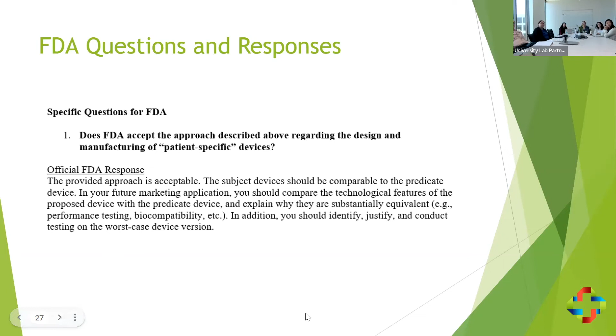All right, so this is one of the questions we got from FDA. I've kind of redacted some stuff in here. Does FDA accept the approach described above regarding the design and manufacturing of patient-specific devices? And they say, the nice thing, the provided approach is acceptable. The subject device should be comparable to the predicate. In addition, identify, justify, and conduct testing on the worst case device version. So it's really nice when they give you very clear feedback. Sometimes it's not very clear feedback.